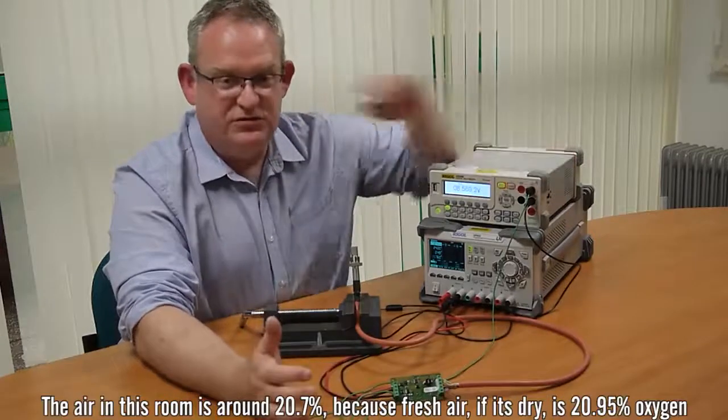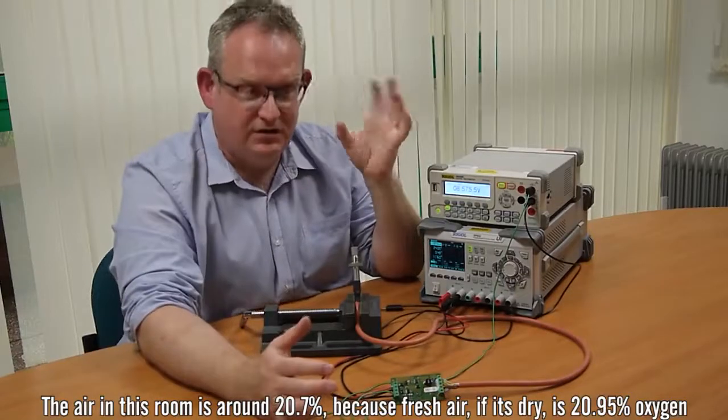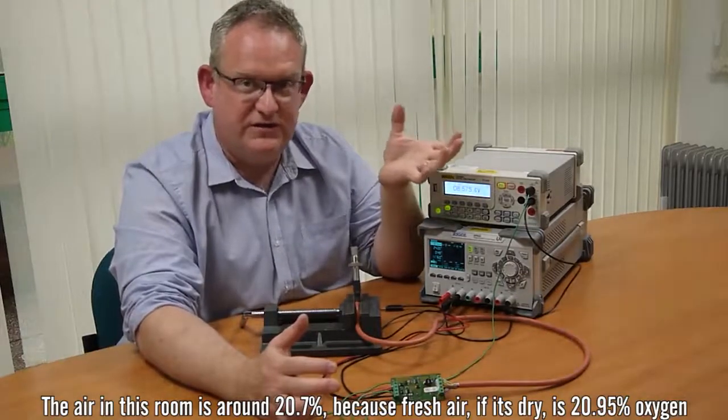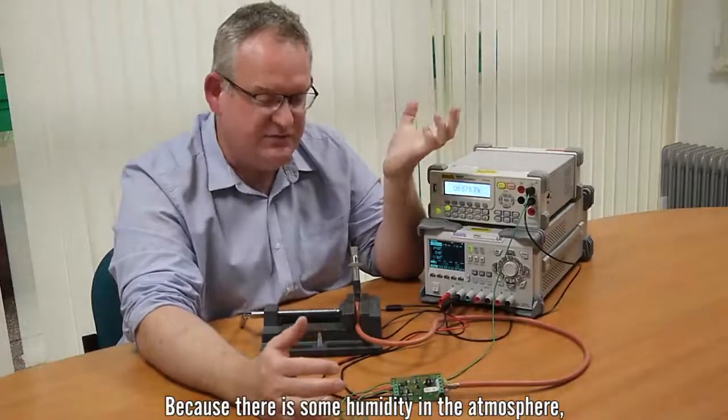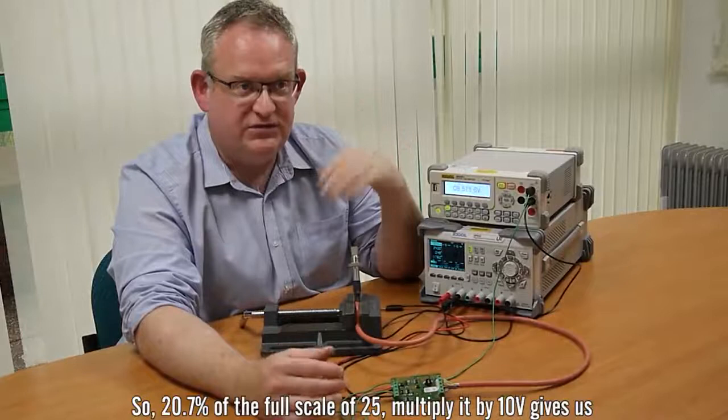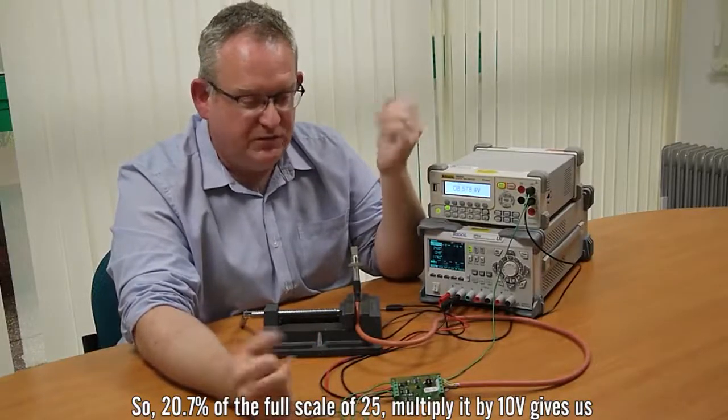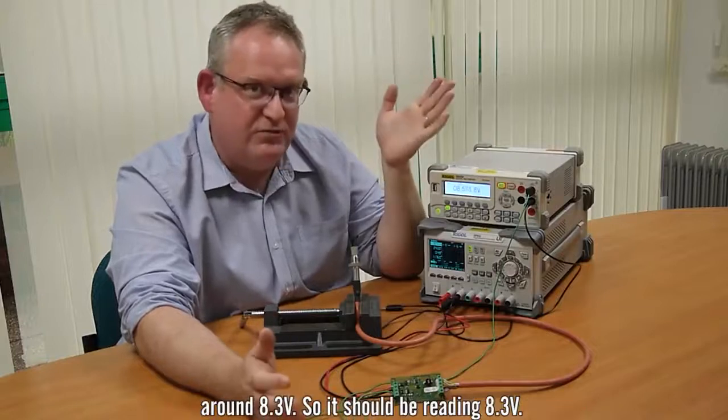The air in this room is around 20.7 percent because of course fresh air is, if it's dry, is 20.95 percent oxygen but because there's some humidity in the atmosphere it's always going to be a bit lower and typically it's 20.7 percent. So 20.7 percent of the full scale of 25 multiplied by 10 volts gives us around 8.3 volts.